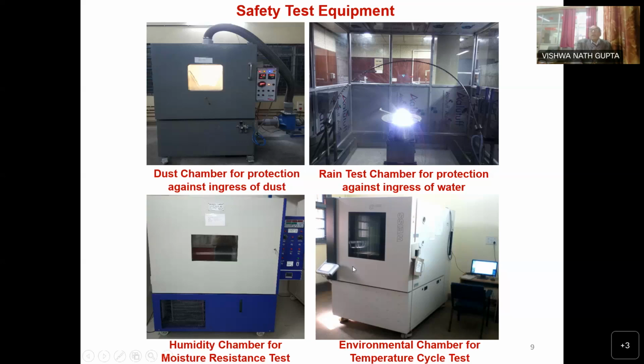These are the environmental chambers for temperature cycle test, a very precise setup. It is used from minus 20 degrees centigrade to 70 degrees centigrade. For example, aviation equipment may go from 20 degrees to minus 20 degrees in the air, so the performance of that equipment can be checked using these chambers.